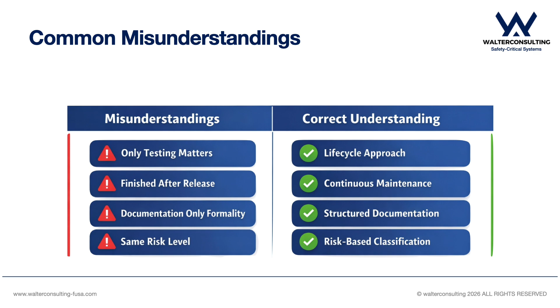There are several common misunderstandings about IEC 62304. One of the most common is that software safety is only about testing. But here is the question. Is testing enough to ensure safe software? In reality, it is about the entire life cycle. Another misconception is that software is finished after release. But software requires continuous maintenance. Some also think documentation is just a formality, but it is essential for traceability and compliance. Another misunderstanding is that all software has the same level of risk. This is why safety classes exist. And finally, software cannot be treated like hardware. It behaves fundamentally differently.